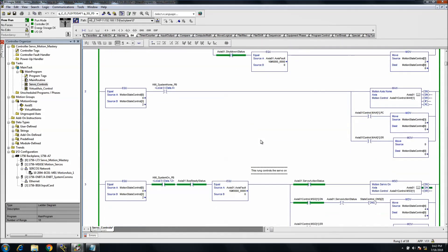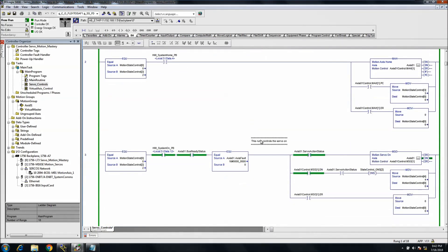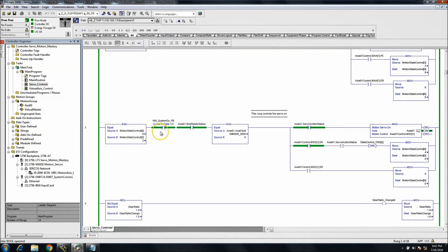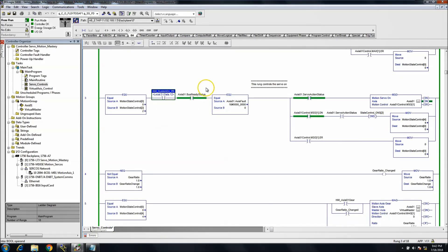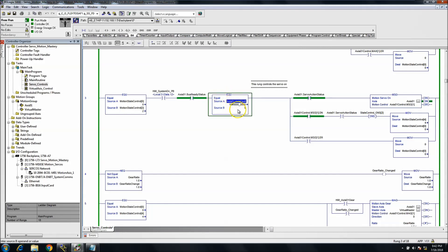Let's say there's no axis faults and everything's good, there's no shutdown status. Then I'll immediately go into where I can home it if I wanted to or I can cut the servo ON. In this case I would like to monitor my bus to make sure my bus is healthy, the bus of my servo controller, and I like to make sure my axis is not in a faulted state.